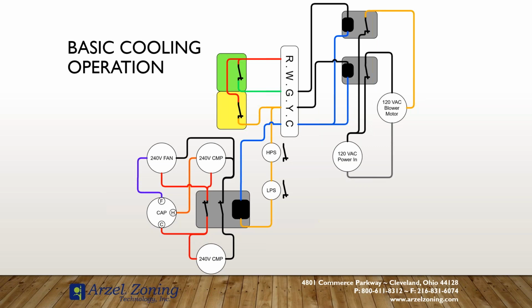But if your low voltage source, everything starts at the thermostat. So we go right back to the thermostat. Step one, verify your thermostat. Check your voltages. If there's no voltage there, that'll be a pretty obvious one in this case. But if you have voltage and things still aren't working, check your resistance, because that'll prove those contacts for you.